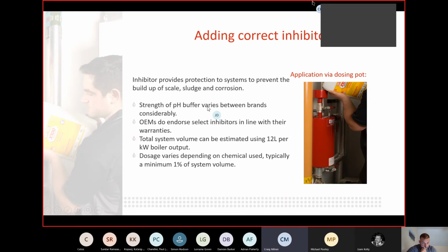Ours is a multi-complex blend. It's not just doing one thing. There's 9, 10 different chemicals in there that are all working together to protect the system. So, like Jay said, you're looking after different metals: copper, aluminium and steel, and then you've got to buffer the pH, so there's multiple things for that. And the good thing with our X100 is looking after limescale control. It is a real benefit of that system that it can look after limescale in a really good way.